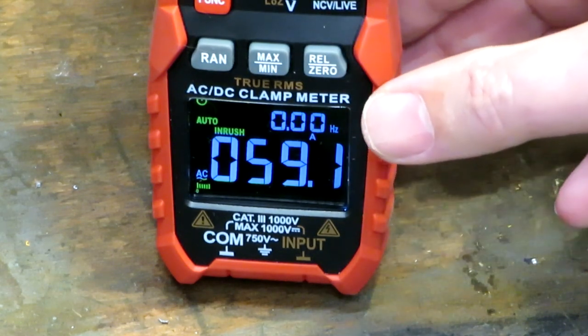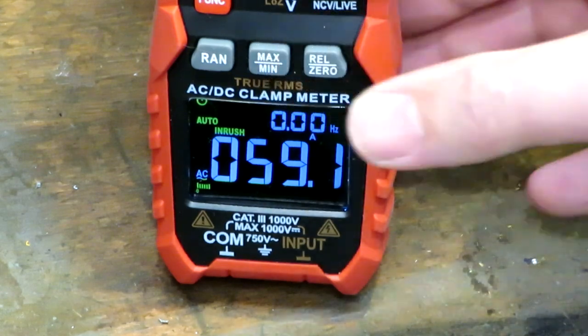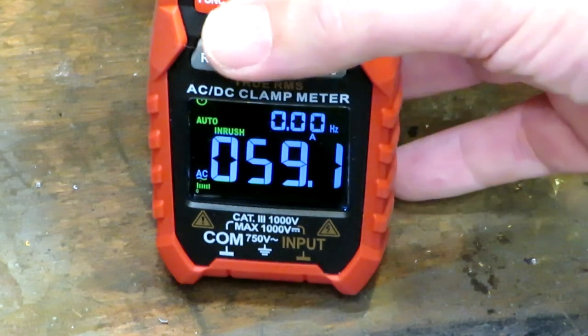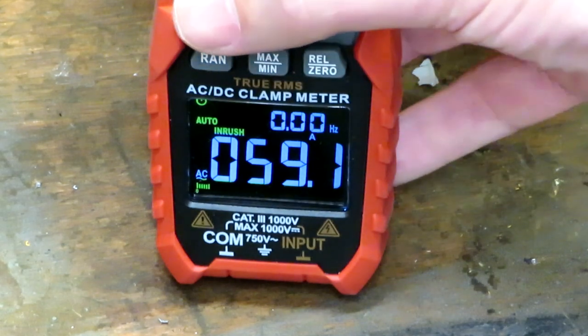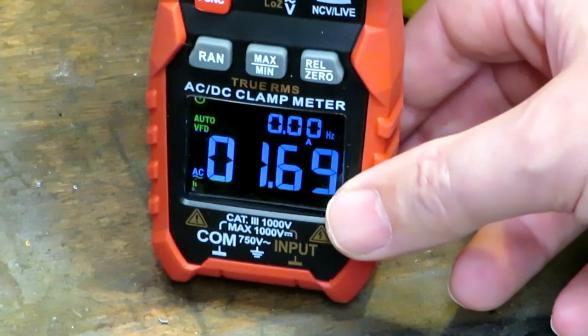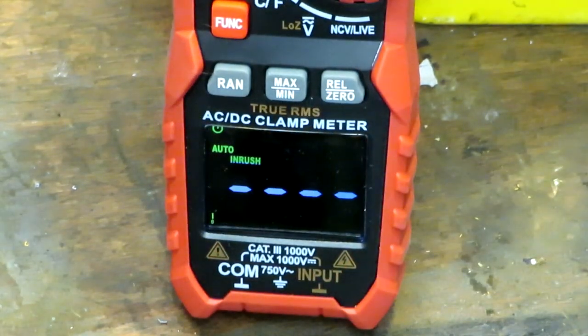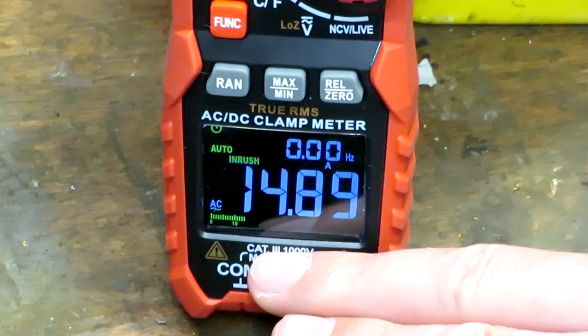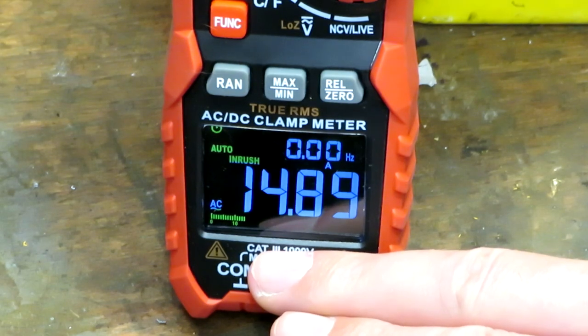So again, if we actually just go back to the standard measuring function, again we'll find that the actual standby current for this transformer is not very high. And again we're now back to our 1.7 amps of quiescent current. And once again. So this time the inrush current was much lower at only 14 amps, and that's because the mains cycle was actually closer to the zero crossing point than it was to the 240 point.